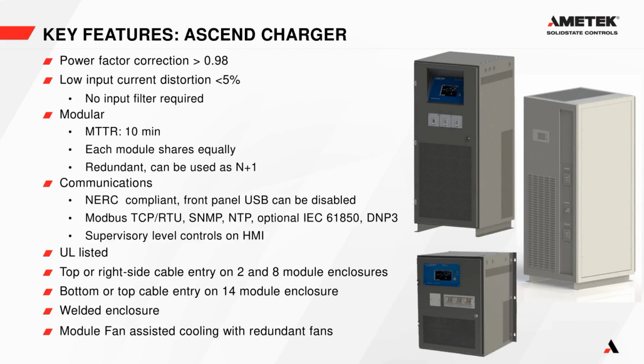For the 2 and 8 module enclosures, we offer top and right side cable entry. We have cutouts or punch outs that the customer can choose to punch out when they decide which kind of cable entry they would like. And the enclosure is welded. And each module has 4 cooling fans, and the 4 fans allow it to be redundant. If one fan fails, we can still supply the output.